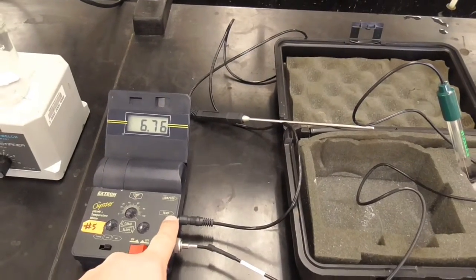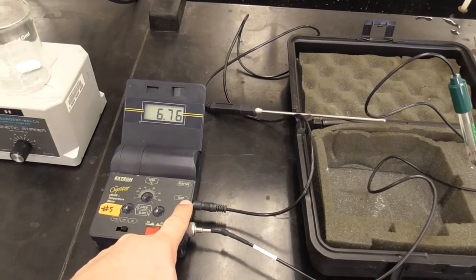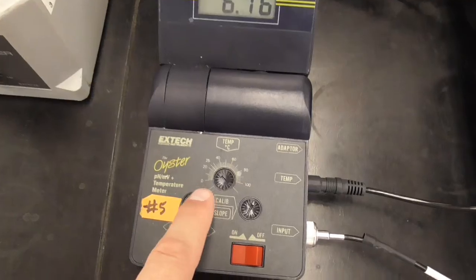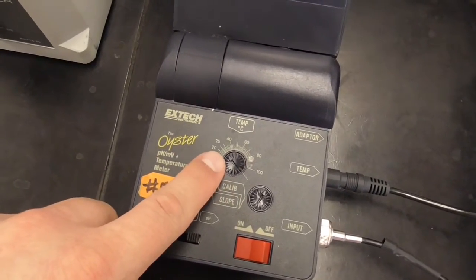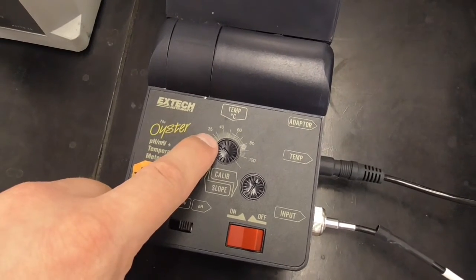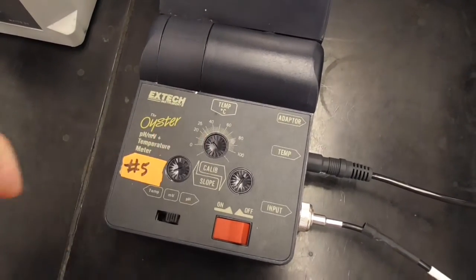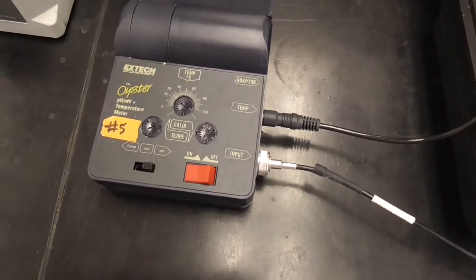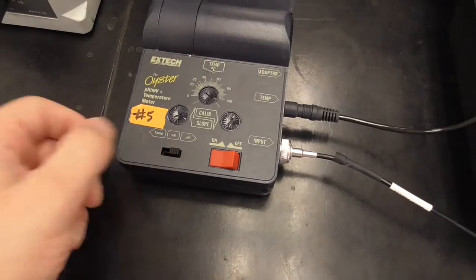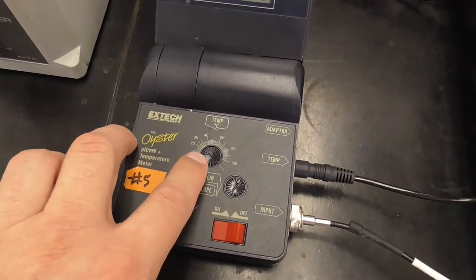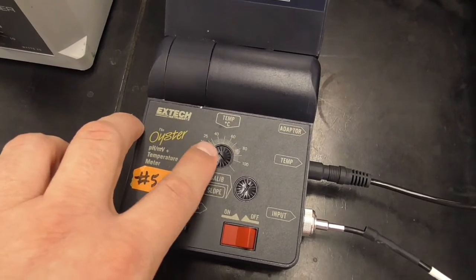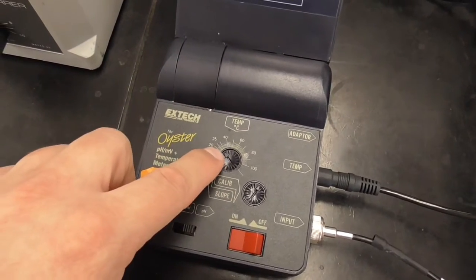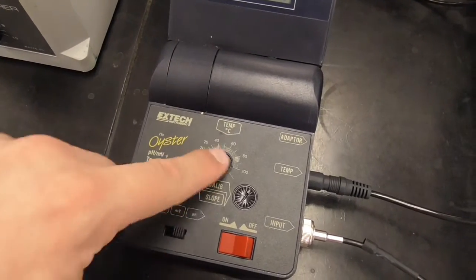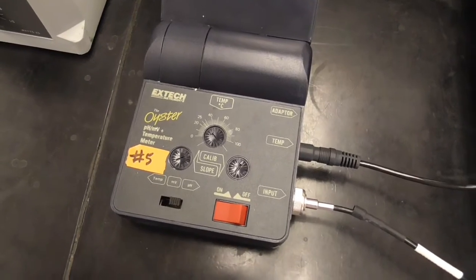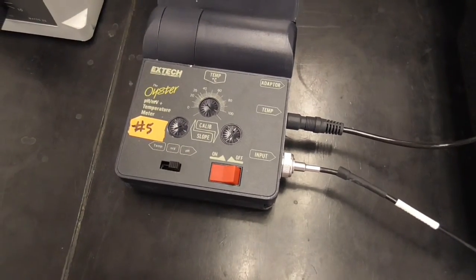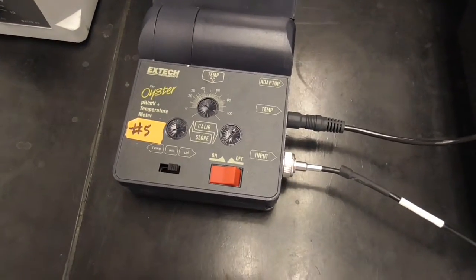Also, I put in a temperature probe. Now, usually the temperature probe, it's not critical. As you can see on the instrument, there is a temperature gauge, and you can see the little arrow on the handle there, and it's pointing between 25 and 30 degrees. Okay, which is what the temperature reads. You slip the indicator over here to the temperature. The main thing with the temperature is to check that this here is pointing roughly in the right direction. I mean, there's no way you're going to be able to tell if it's 28 or 27 or 26, but as long as somebody hasn't accidentally moved it to like 60 degrees or something like that, or down to 0, you should be fine, because sometimes people hit the wrong button when they're doing this.